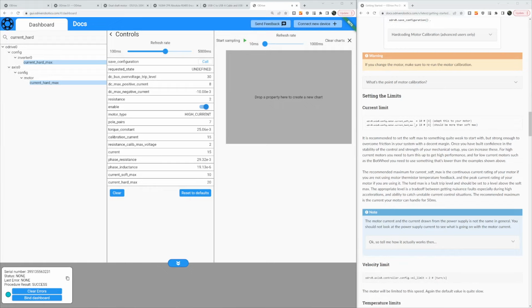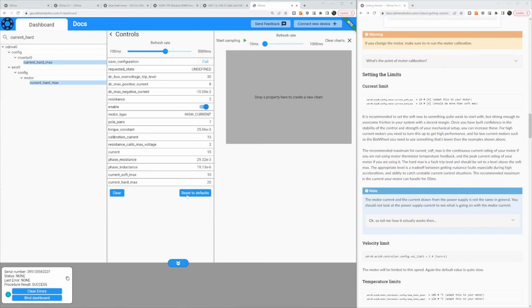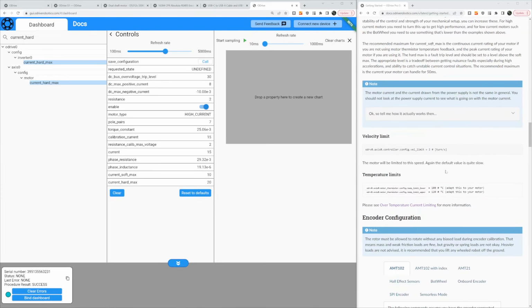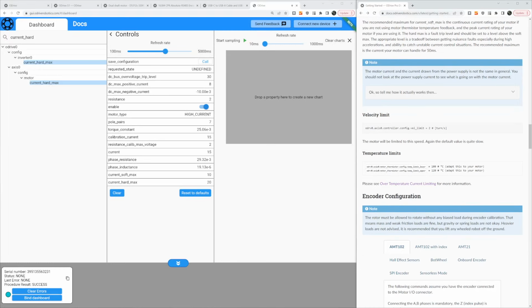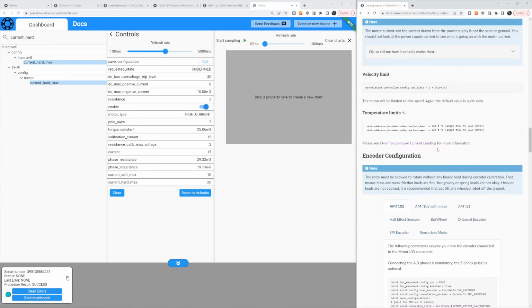So looks like the softmax is already 10. That's what I was going for, and the hardmax is 20. I think that's good to start with here. On a motor whose rated current is lower, you would have to lower this, of course. And if this is very close to the rated current, then this wouldn't be a nice and low value to start with. You might want to lower it as well. In this case, 10 amps is fairly medium low for this motor, so it's a good place to start.